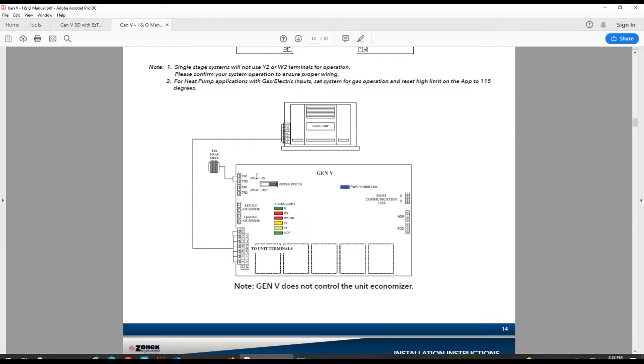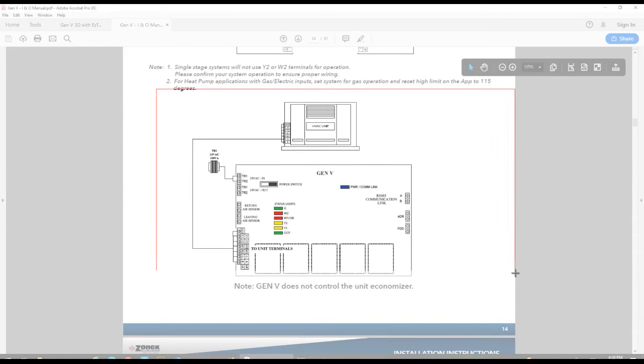Alright, last portion of the wiring is wiring in our rooftop or split system. So using 18/7 or 8, you'll go ahead and wire it in accordingly. Off the Gen V, you're going to wire to your unit and match it up: R, G, Y1, Y2, W1, W2, and if you have that OCP terminal, you can land the OCP. Just match them up according to what your rooftop unit's operation is.